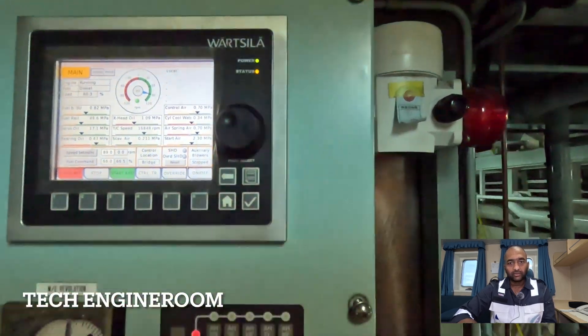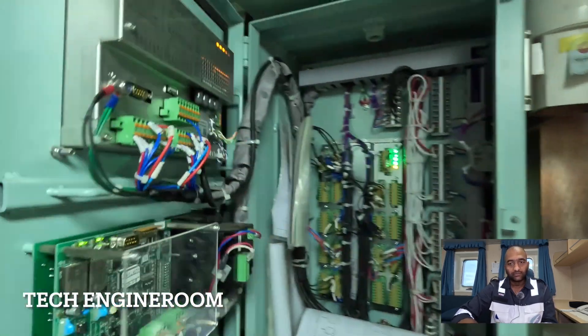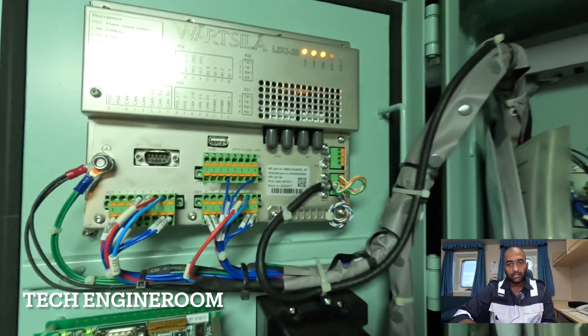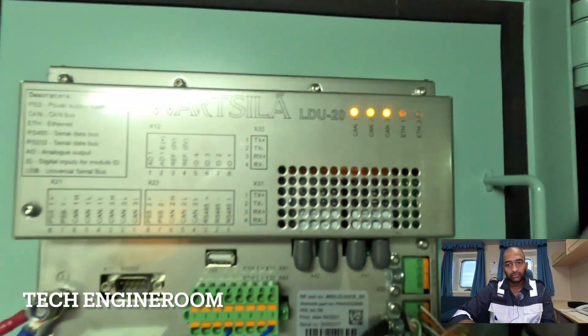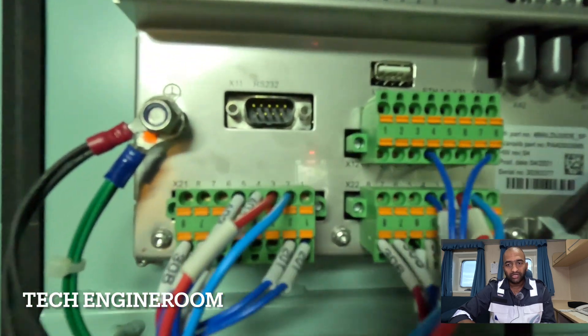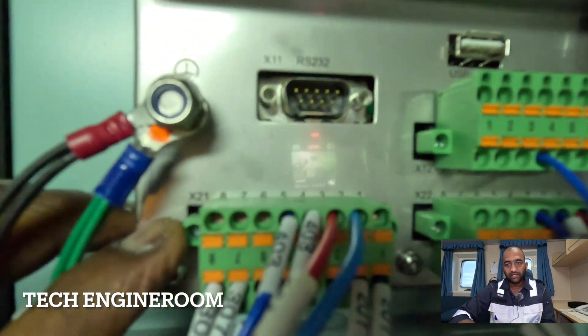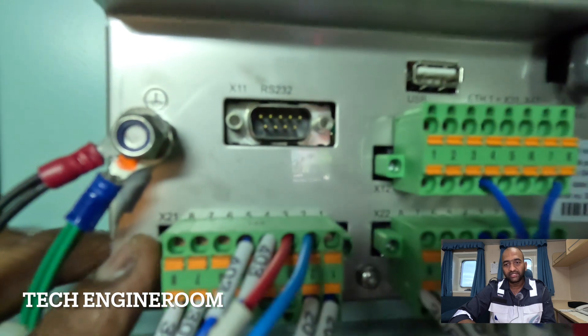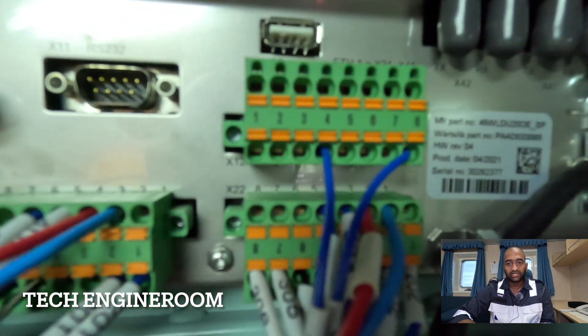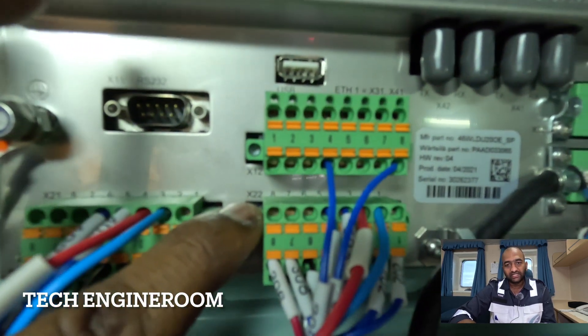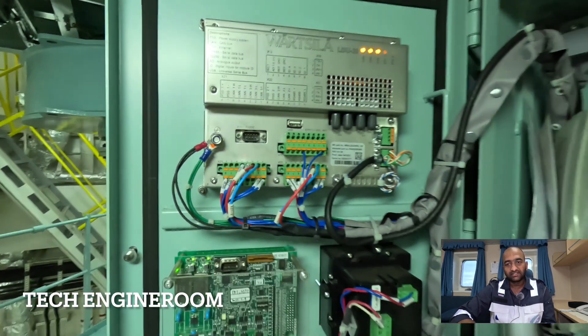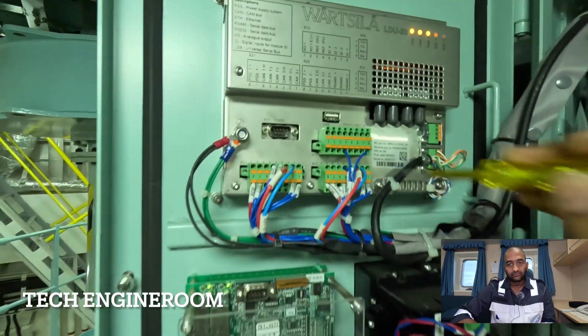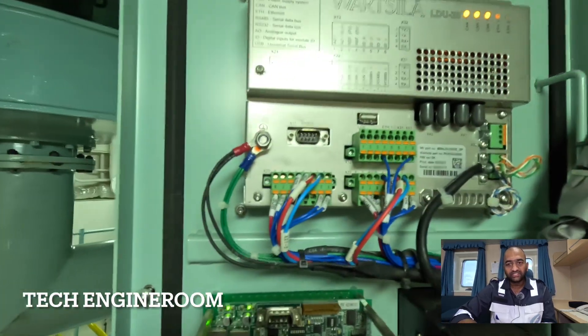So then engineers, how to reset these alarms? First open this panel and you can find these two plugs - one is x21 and one is x22. These two plugs we have to remove to reset this frozen LDU, which should be done in systematic order. First we should remove x22.